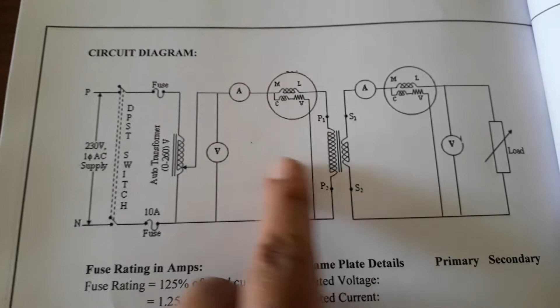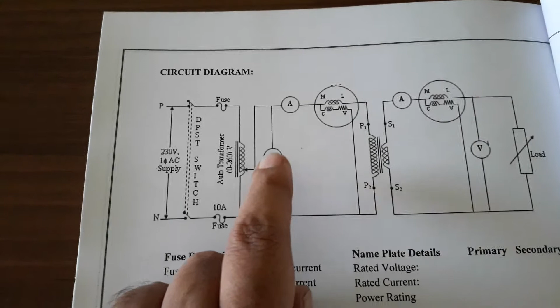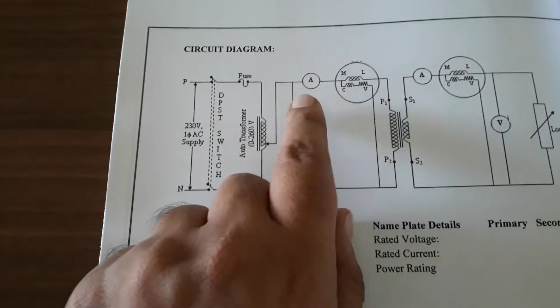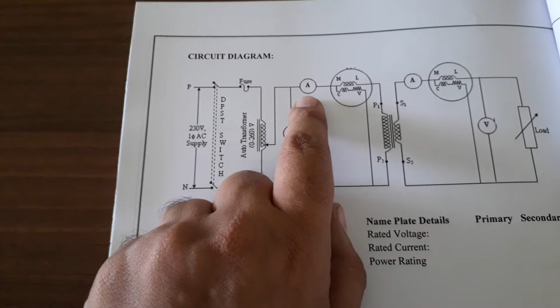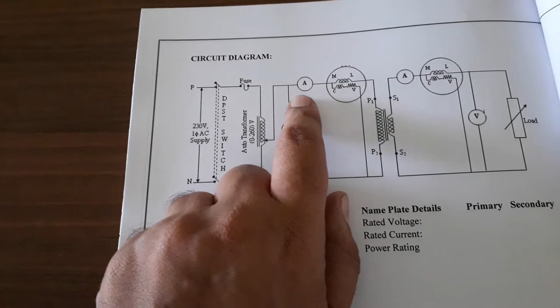Now here you have a circuit. Our primary voltage of the transformer is 230 volts. In our laboratory the available voltmeter ranges are 150 and 300 volts, so we choose the 300 volt voltmeter for single phase. For the ammeter, the rated current of the transformer is 4.3, so you can choose a 5 amp ammeter or a 10 amp ammeter.